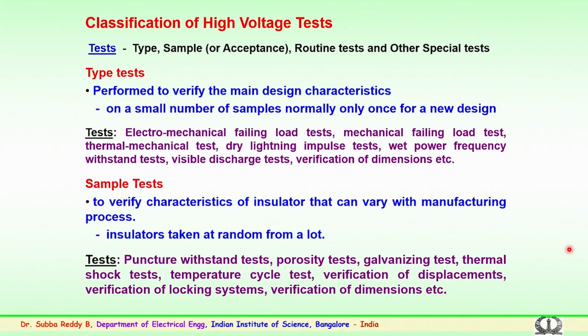The sample test, or acceptance test, is basically to verify the characteristics of insulators that could vary with the manufacturing process. Normally, insulators are taken at random from a lot of an existing type. The sample test consists of the puncture withstand test, where for a particular voltage level the insulator should not puncture, and the porosity test to check the material properties, so that there is no porosity in the insulation. The galvanizing test checks that proper galvanizing has been carried out for the metallic pin and the cap.